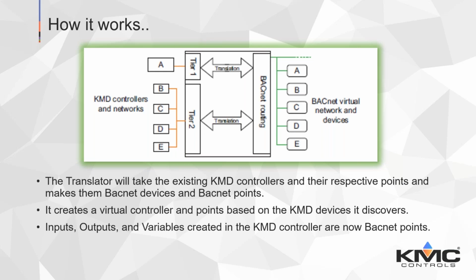Your inputs, outputs, and variables created in KMD are now BACnet points, and they have the same rules that BACnet applies. So you can override them, they have priority, and they have all the same functions that you would use when you're working with BACnet points.